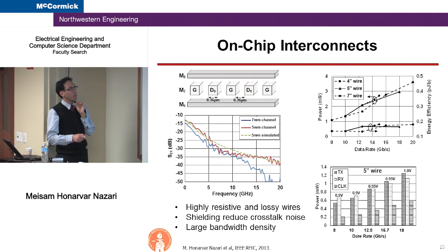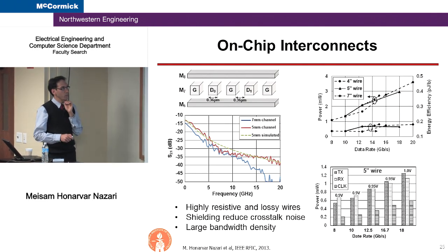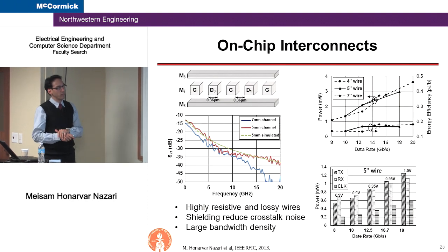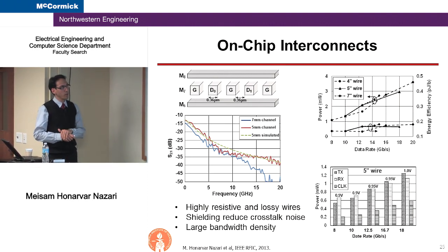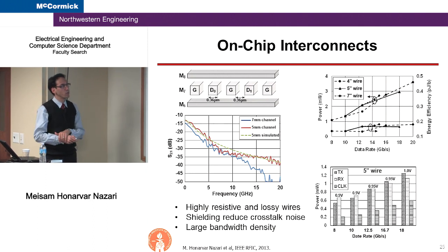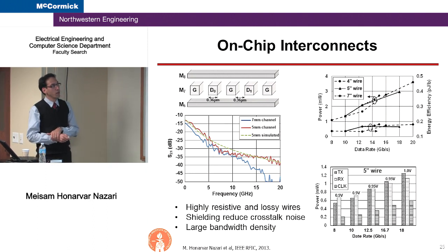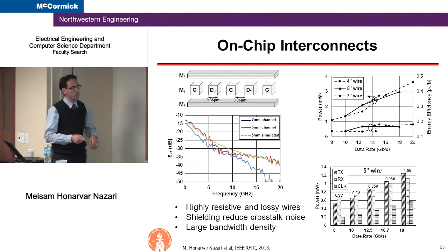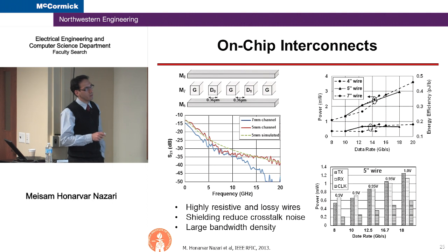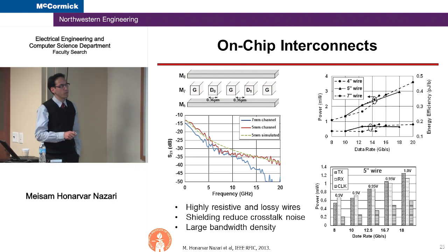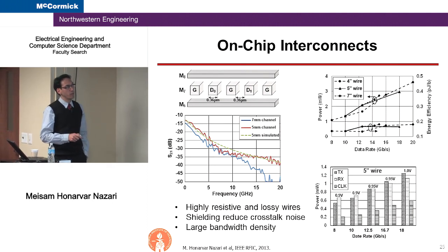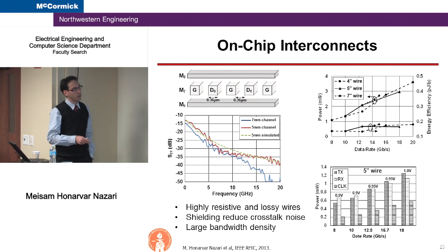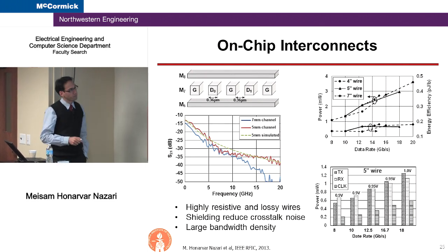So one thing that needs to be noted is that because we are using single-ended signaling, we need to also be careful about crosstalk between different channels. So what we have done to compensate for it is to use ground shields between different channels. We insert ground shields between adjacent channels so that we minimize the amount of crosstalk between the two channels.